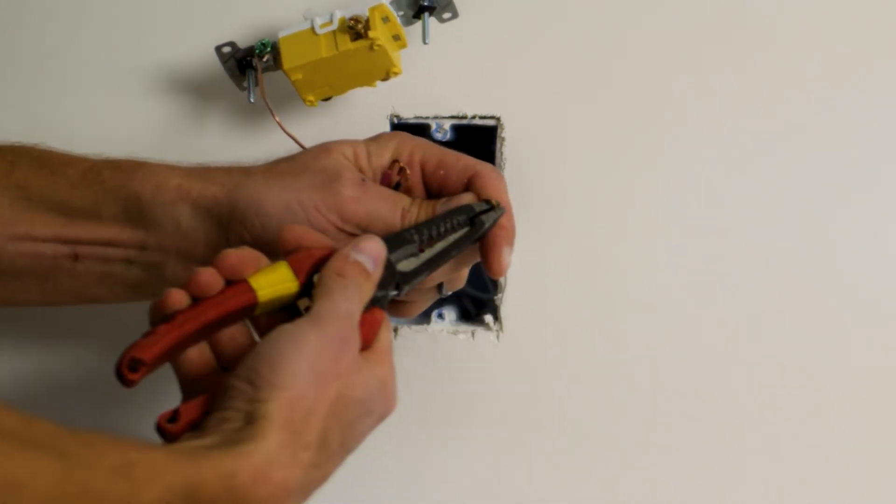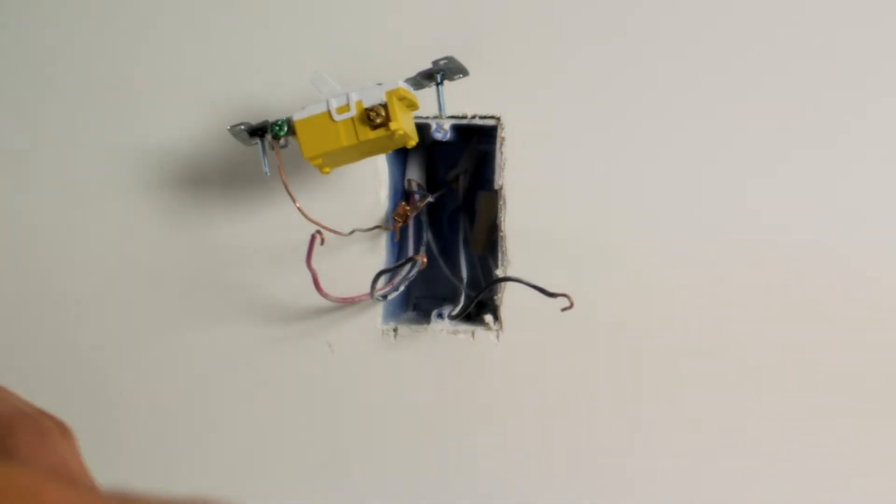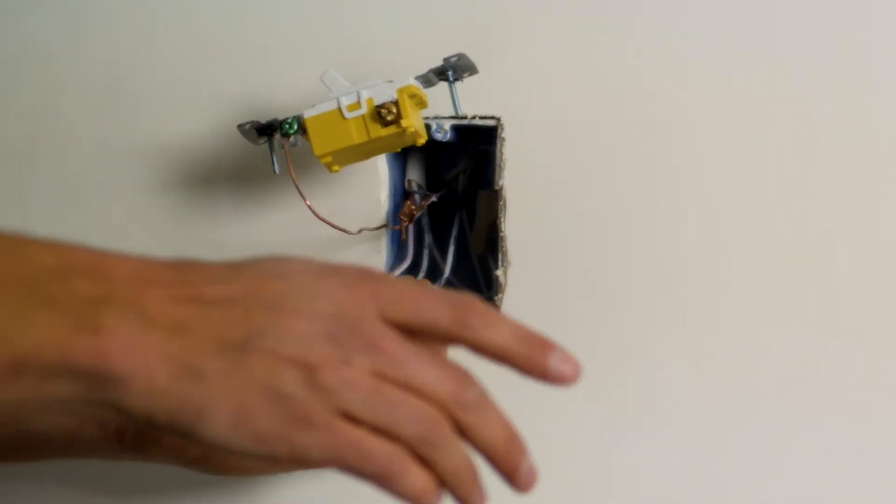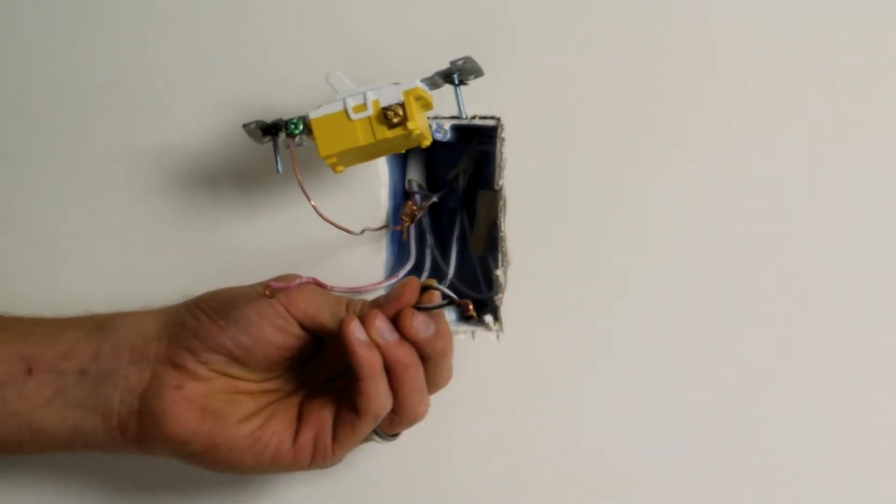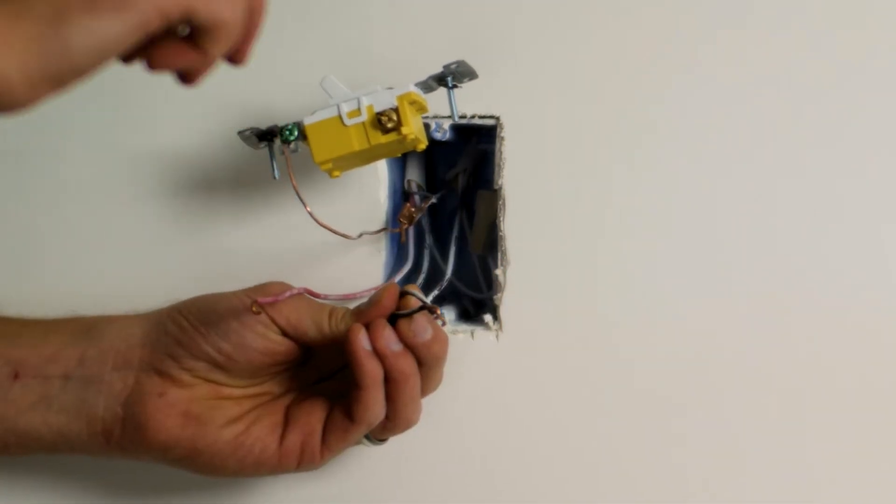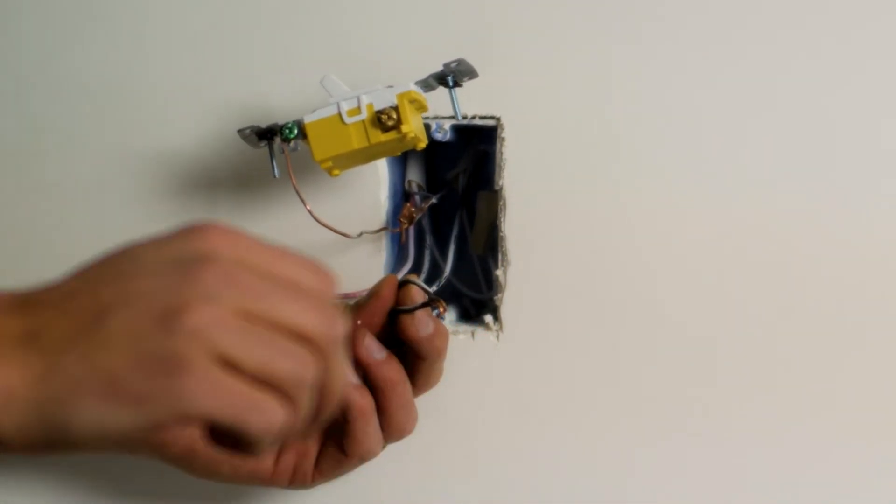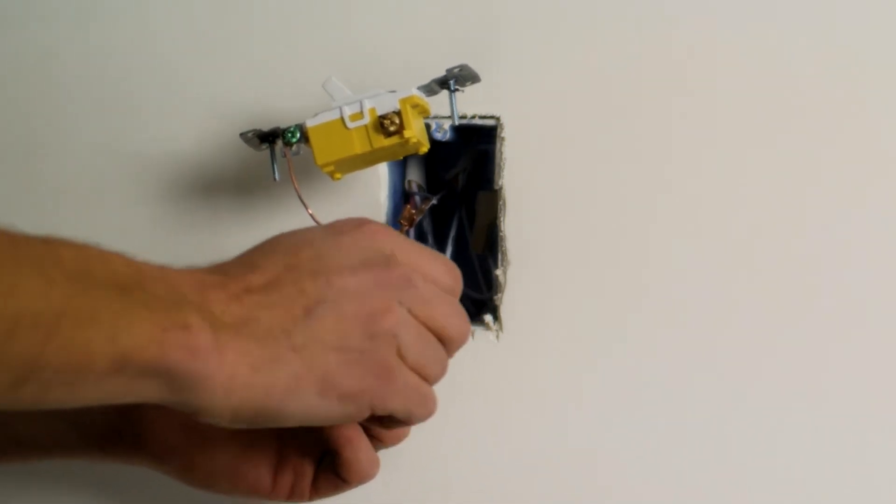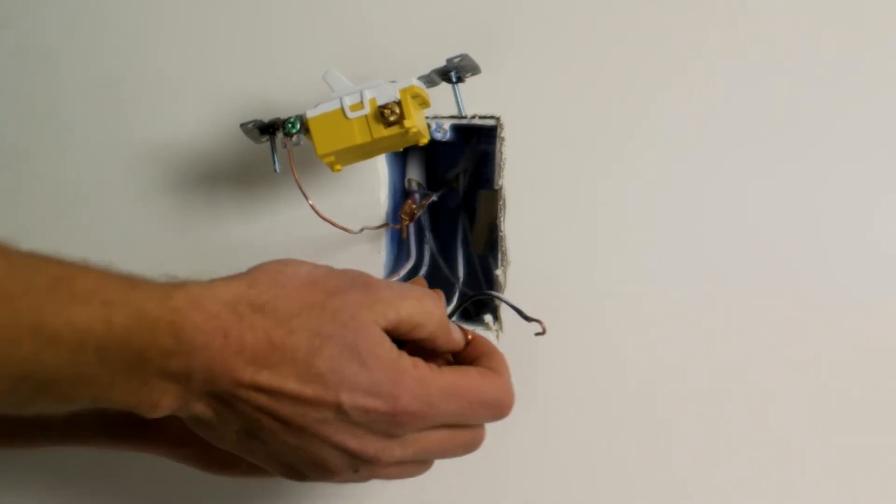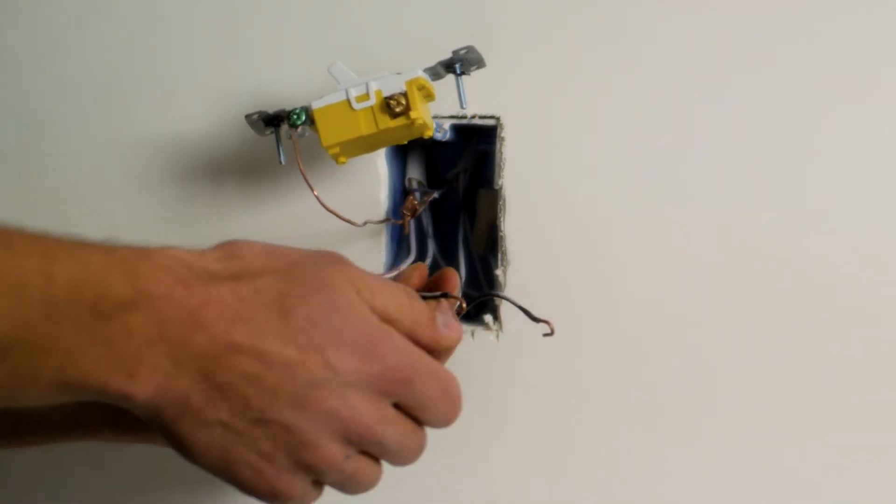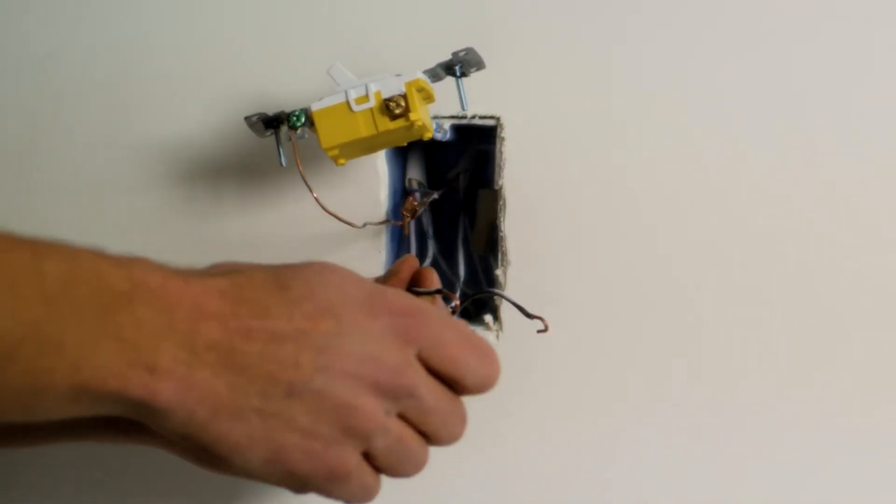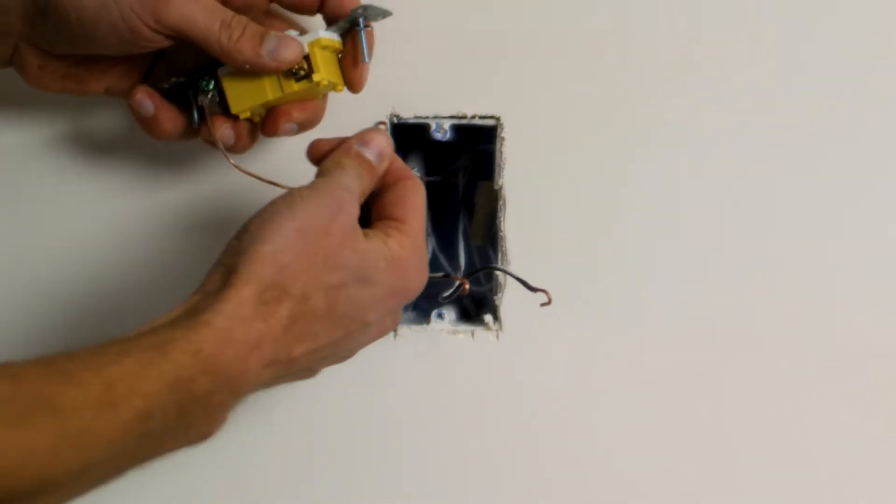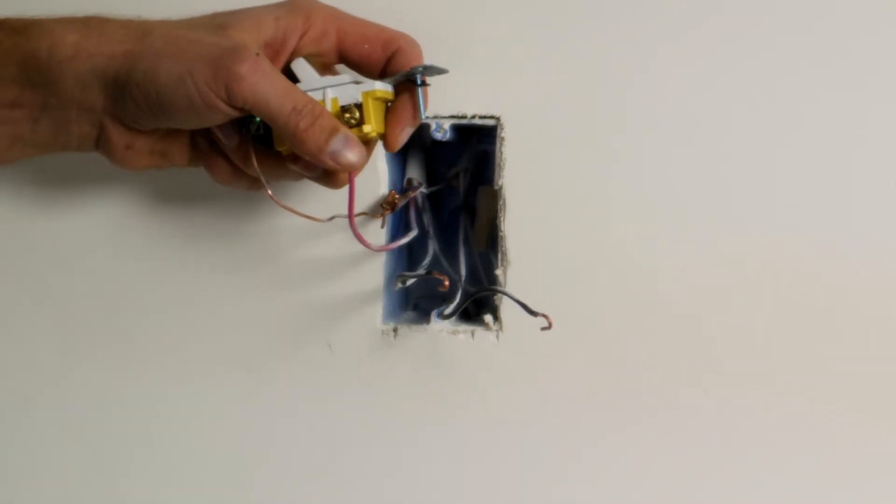I'm going to repeat the process right on the end of each of my conductors. I'm going to bend them to the right. If any of these conductors have been damaged—for instance, when these were pre-twisted for the purpose of obtaining temporary overhead lighting, if they were overly twisted, there's a real possibility they had suffered damage. In that case, I want to look for a deep nick or any type of compromised point in the copper conductor, then I want to cut that off and re-strip it so I've got solid, intact copper conductor.